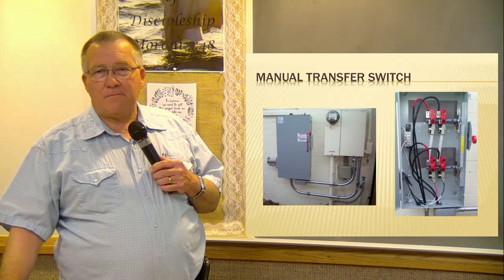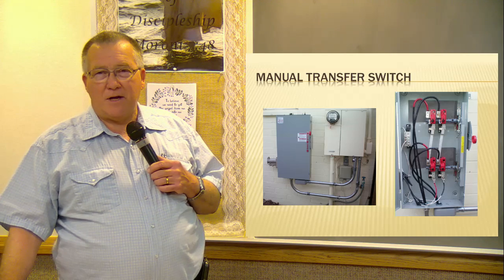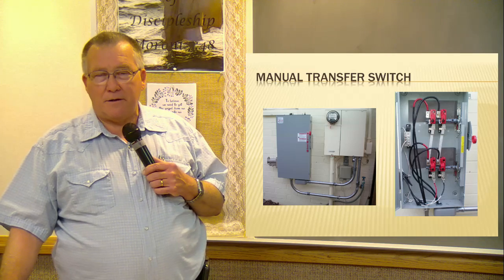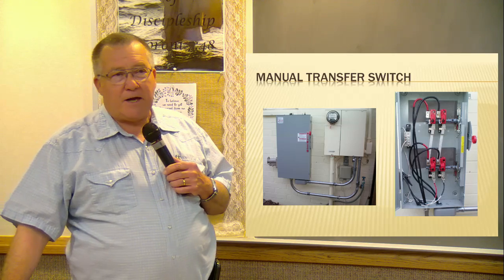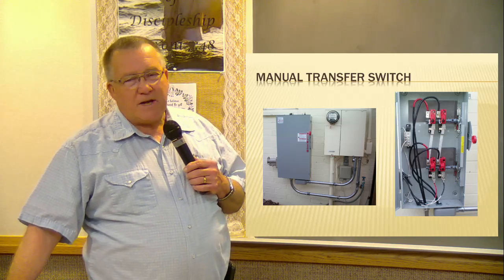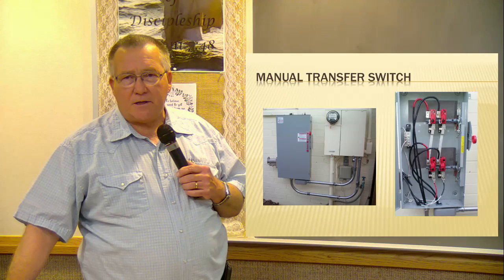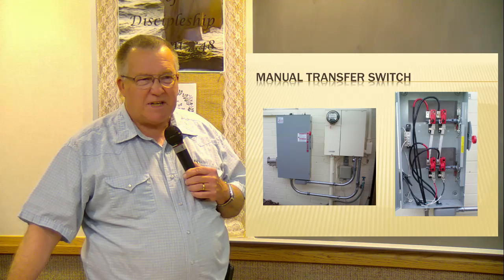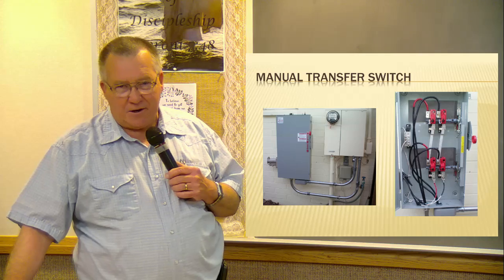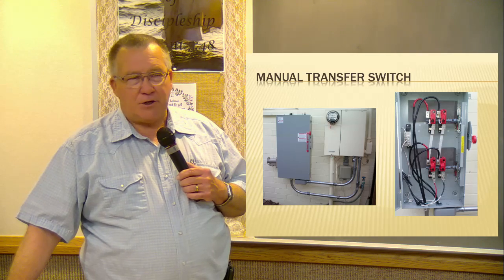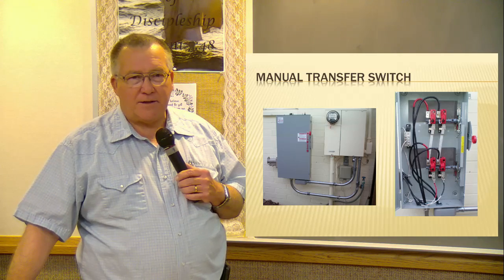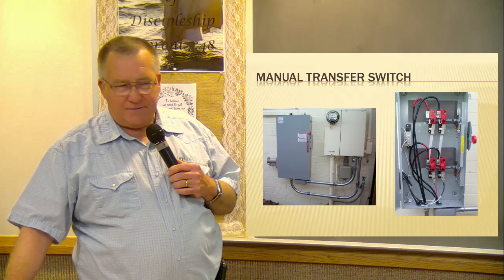You'd need about twice, or really about 3 times that power just to start it. A 3 kilowatt generator, a 3,000 watt generator, I've seen lots of those start 1-ton air conditioners. A 2kW will not start it, a 3 will, and a 4 or 5 definitely will.